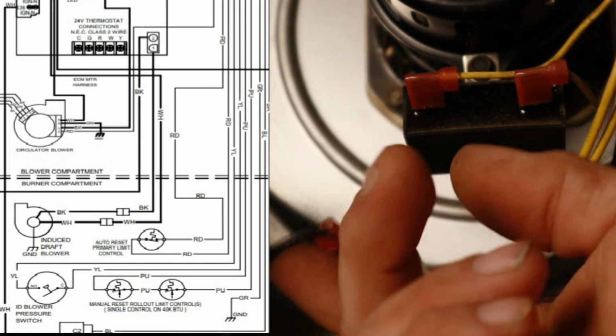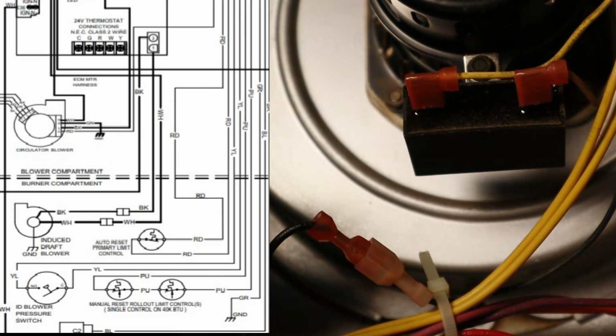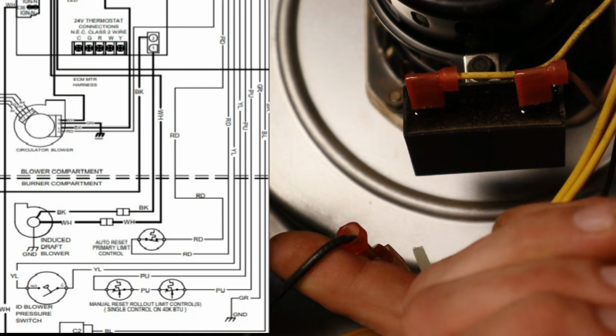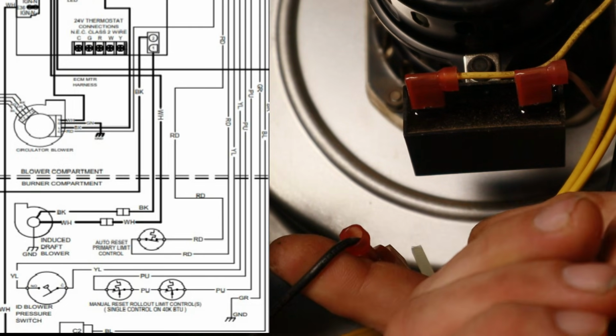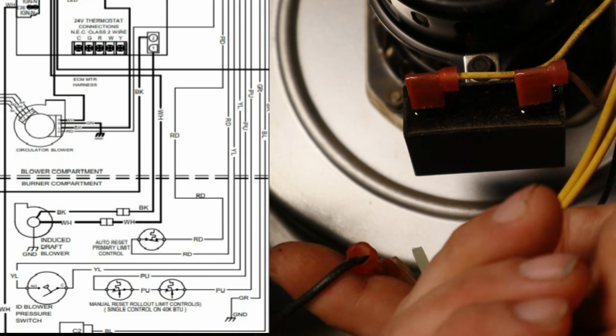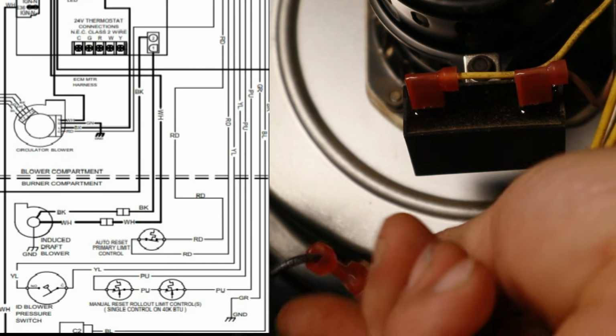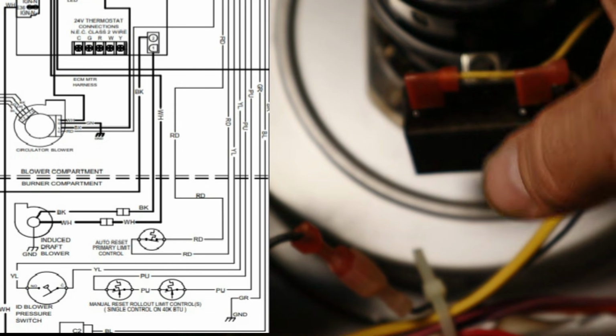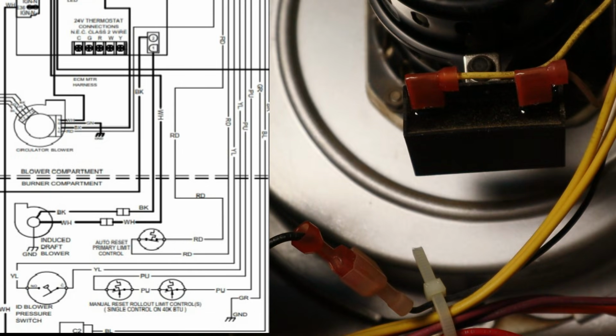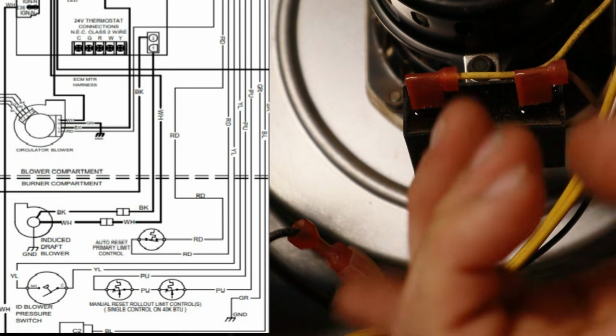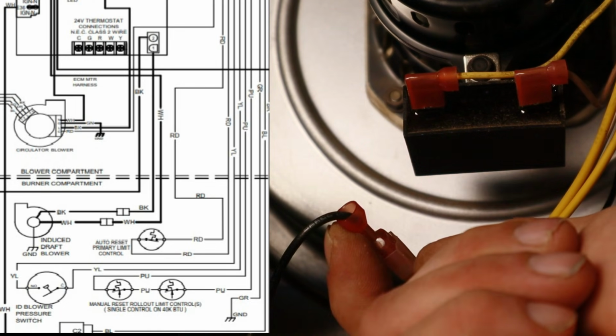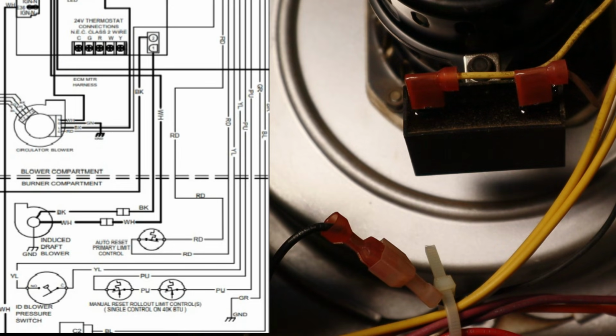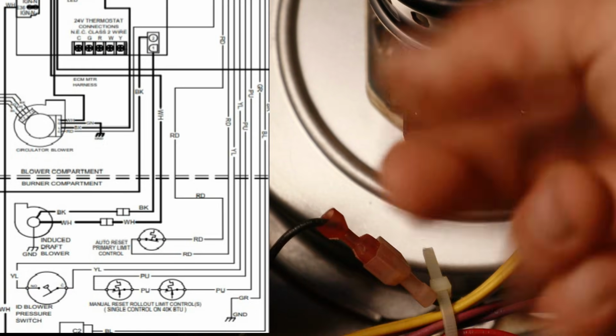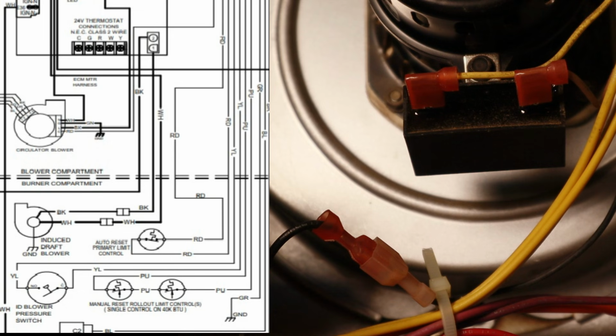So we were able to trace off of the control board that little Molex plug sending 115, 120, whatever it may be. I think we made 125, right? So 125 volts coming up to this wire. With it connected, we should have power to run this inducer motor so long as our control module is actually working. So if we didn't have 120 volts here and we had 24 volts on our W terminal, meaning our thermostat was actually sending out the call for heat, we could have a bad Molex plug that's not sending power up to this inducer motor, or we could even have a bad control board.